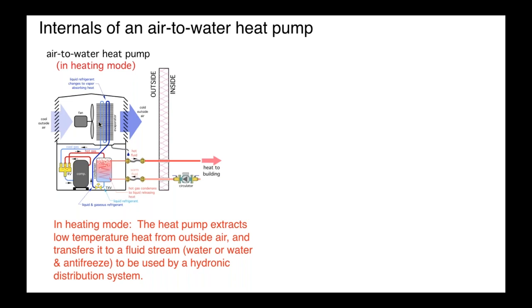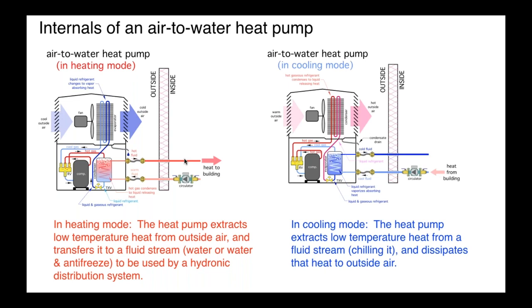And then we're sending that hot gas into a water-cooled condenser. In this case, we're passing a stream of water from a hydronic system through a heat exchanger, absorbing the heat from that condenser, and then taking that heat in and distributing it through the building. And like most heat pumps today, we have a reversing valve. So that same machine can go to a chilled water production mode in the summer, where we are extracting heat from a stream of water.